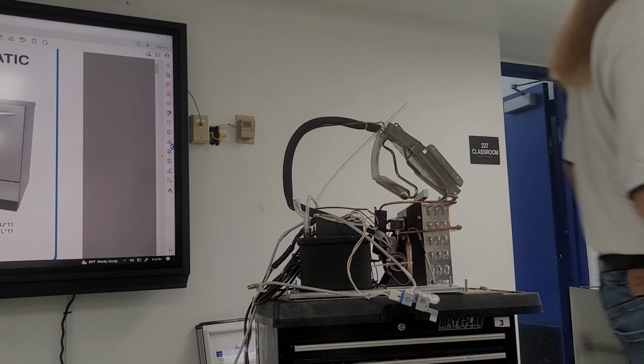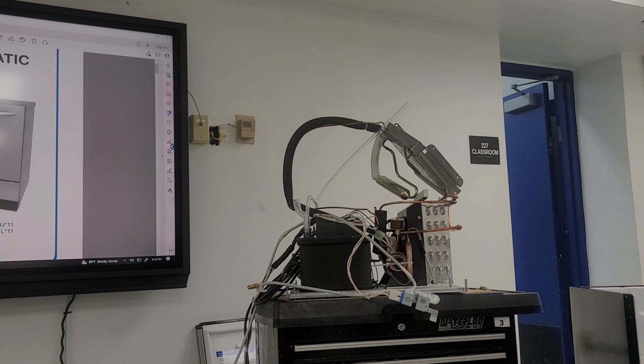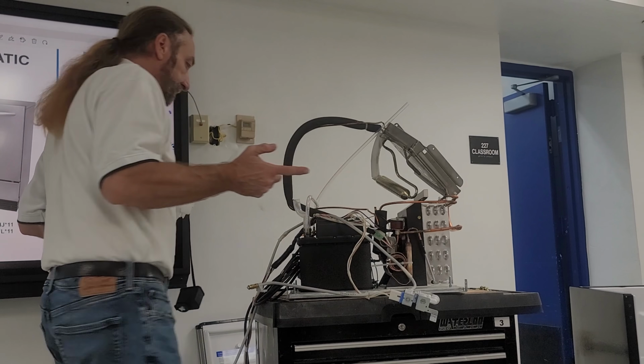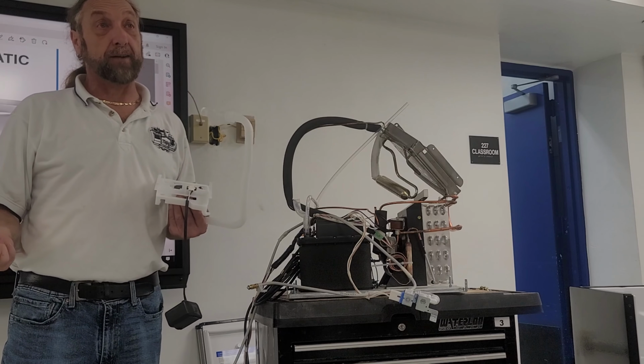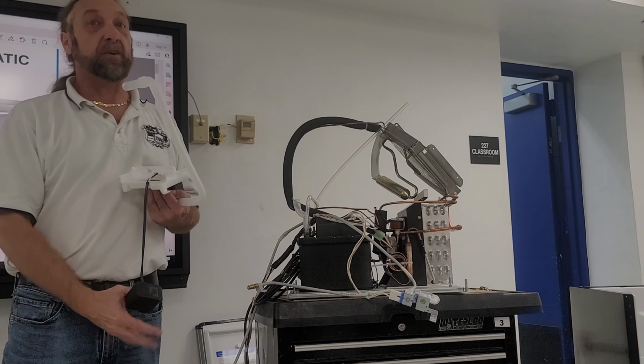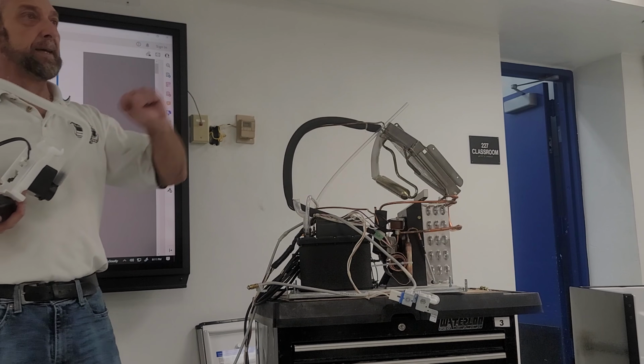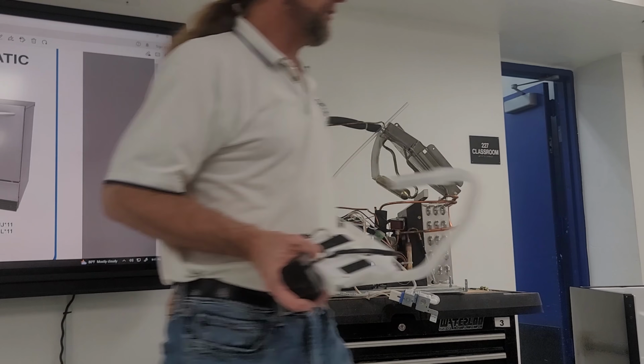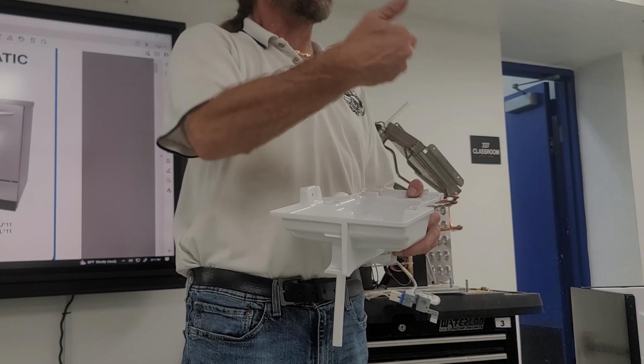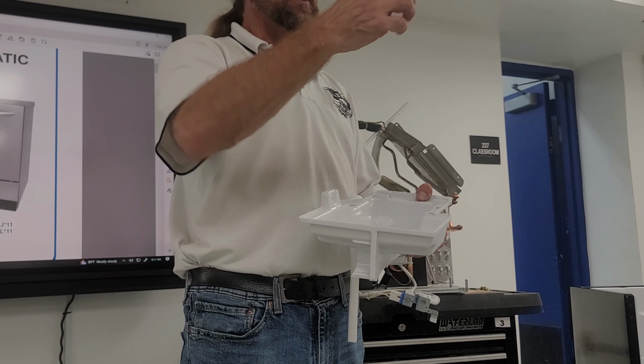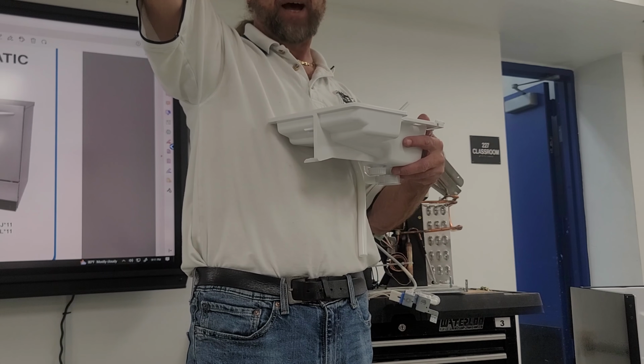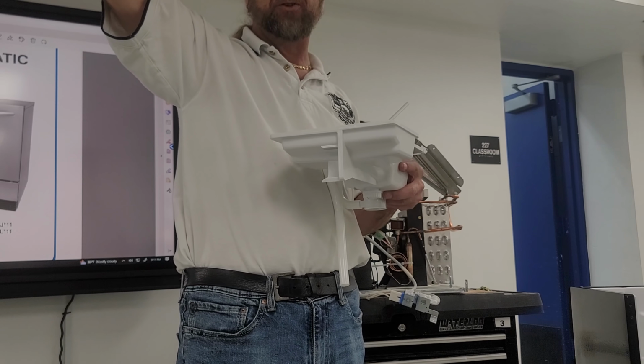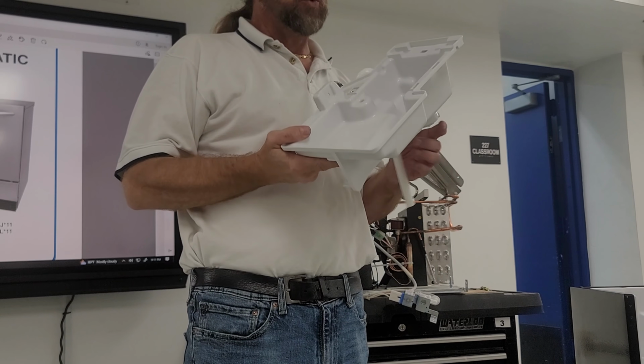Normally it's not timed. You know what I did not see on this particular unit? I did not show you, now that you mentioned that. This particular model does not have the water level sensor. Oh. So how does this one know when to drop the ice? Question, anybody got the answer? I said the water level sensor on the newer models is what tells it to drop the ice. This reservoir here, when it fills up with water, there's a sensor in here that's sensing how much water's coming in. When it's circulating, it freezes, and that water starts to drop as it's turning to ice up top. The water level sensor sees it gets low enough, it knows that turned to ice, and it would stop dropping ice. But this one doesn't have the level sensor.